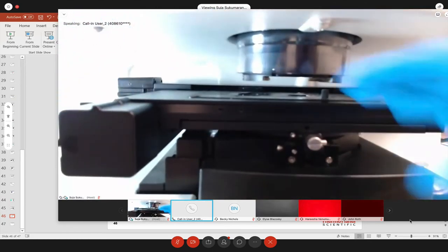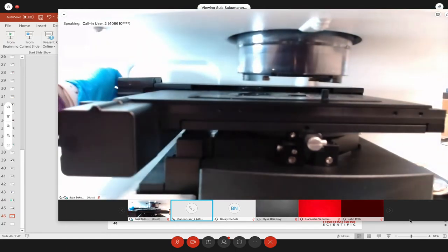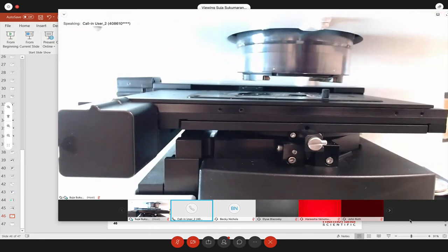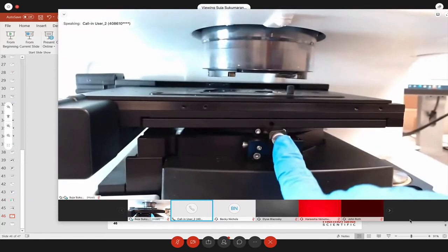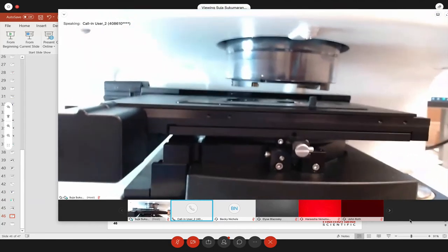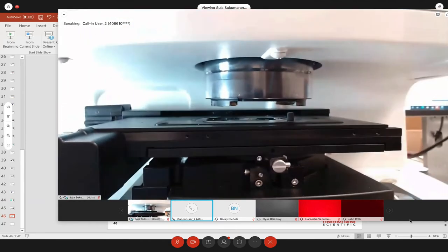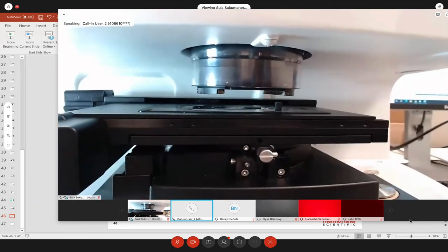And again, just move the stage to one end and it will come right out from there. Just pull it off, or you can even take the stage out. Very simple, just one metal screw right here. It just goes the other way and the stage comes off. You have two connectors, but do everything when the instrument is completely off. So those are the key things.